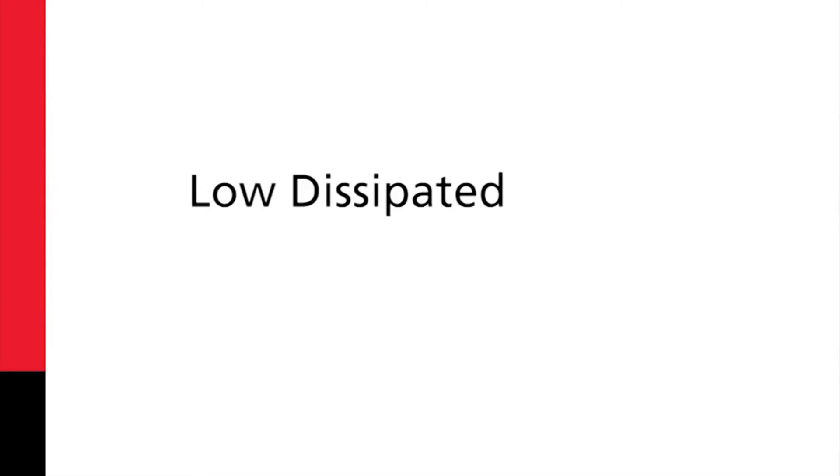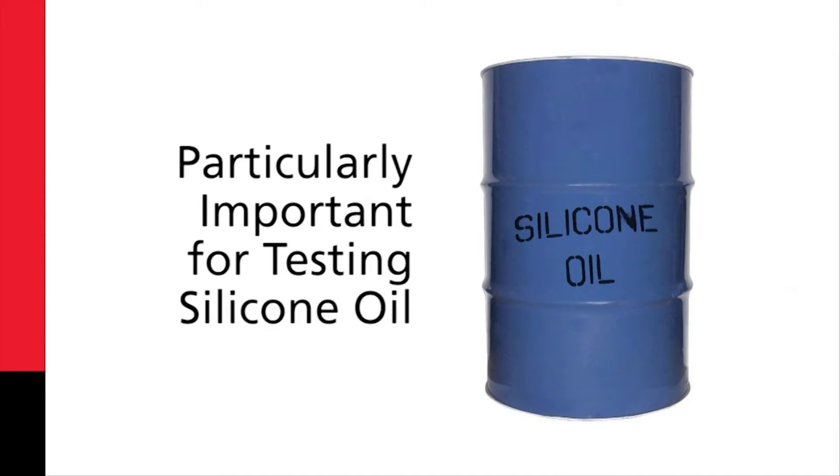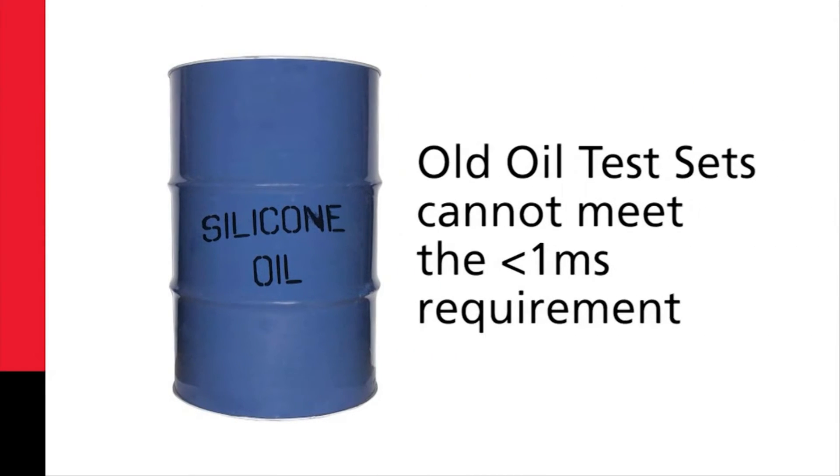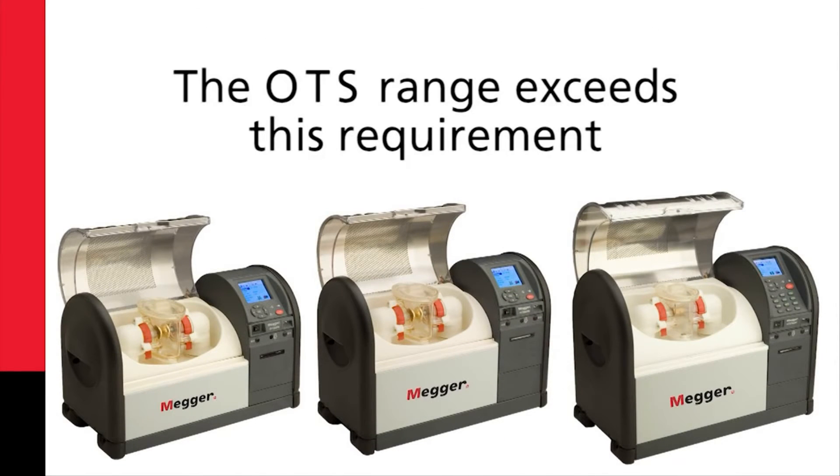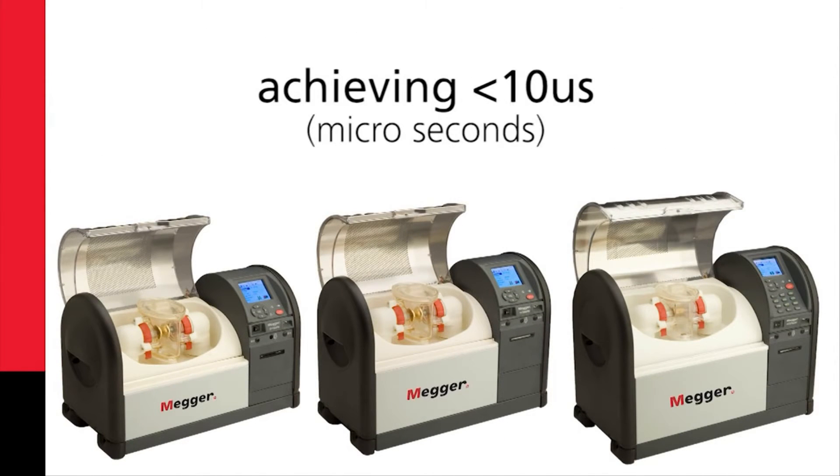Low dissipated power and fast breakdown is particularly important for testing silicone oil. Many old oil test sets cannot meet the less than one millisecond requirement for silicone oil. The OTS range exceeds this requirement, achieving less than 10 microseconds.